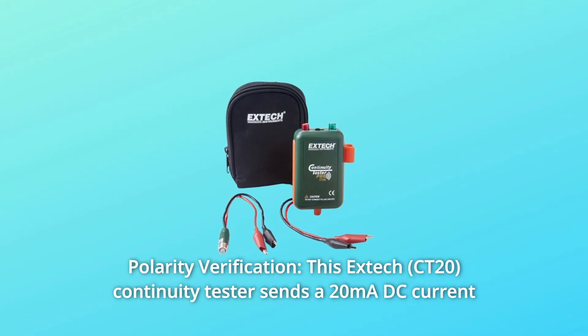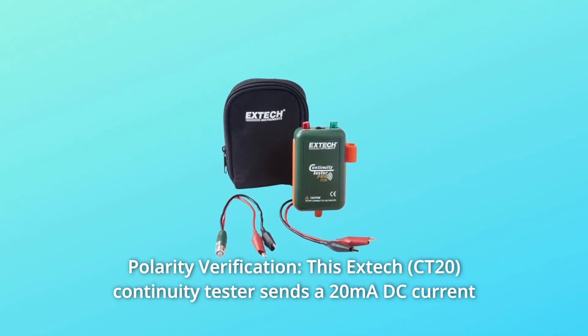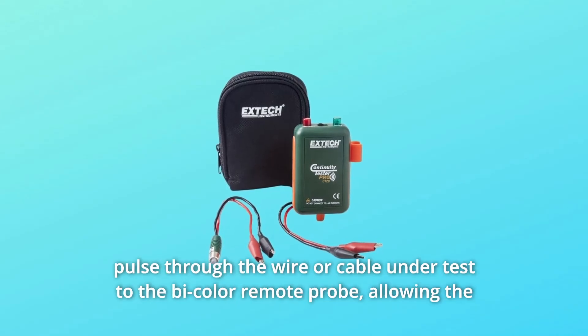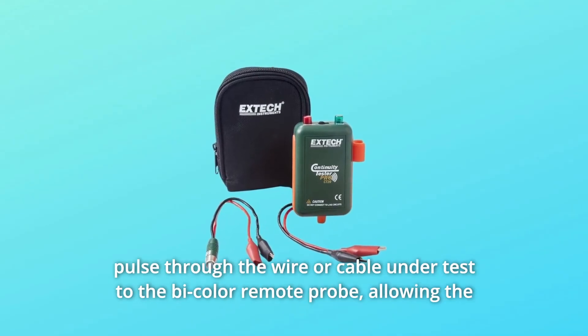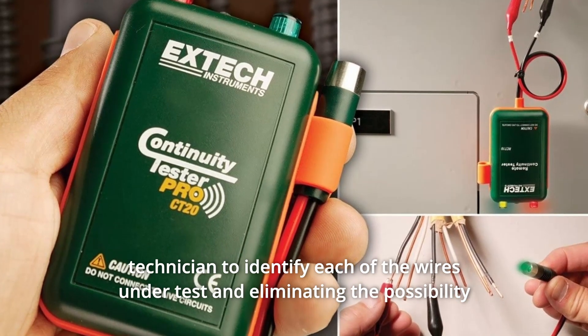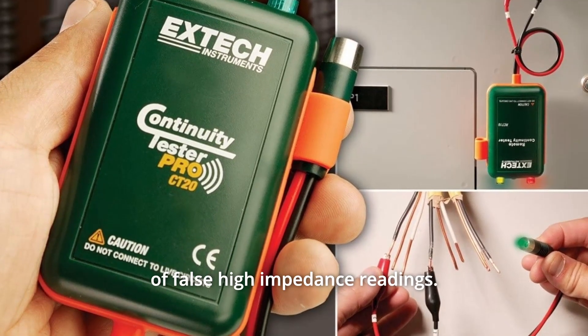Number 4: Polarity Verification. This Extech continuity tester sends a 20mA DC current pulse through the wire or cable under test to the bi-color remote probe, allowing the technician to identify each of the wires under test and eliminating the possibility of false high-impedance readings.